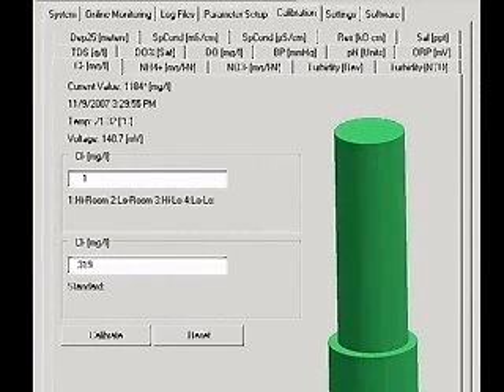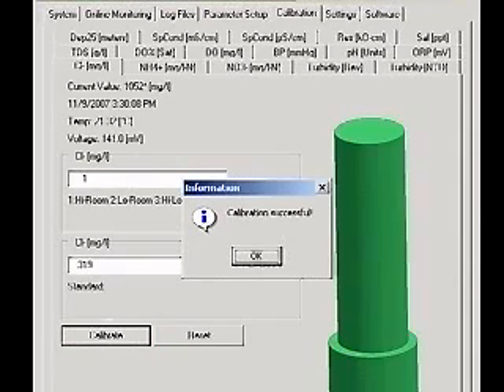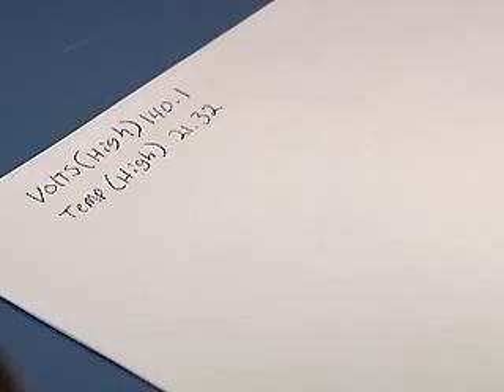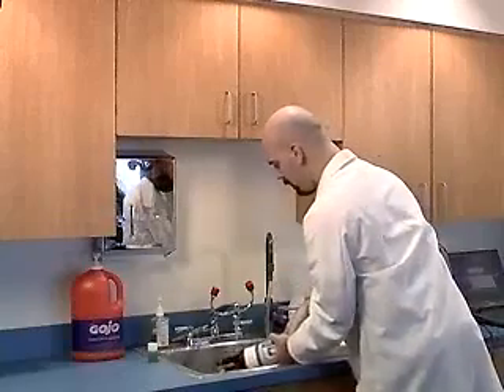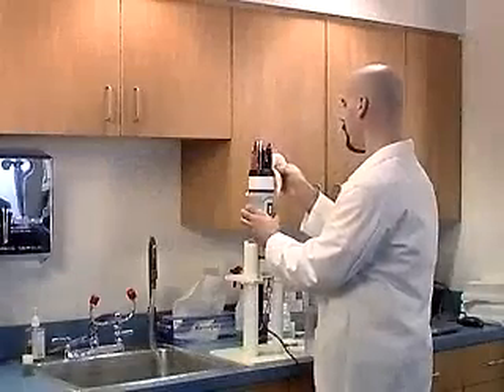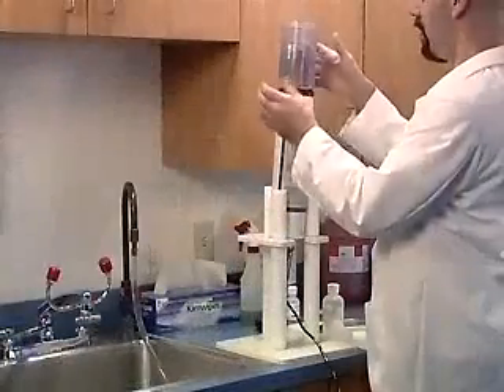When the readings are stable, type a value of 1 in the first box to designate the high standard. Type 359 into the second box and click Calibrate. A calibration successful message will appear. Record the temperature and voltage reading. Rinse the cup and sensors with deionized water and dry them.